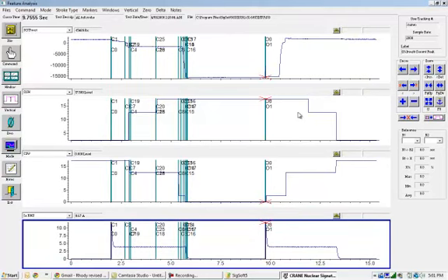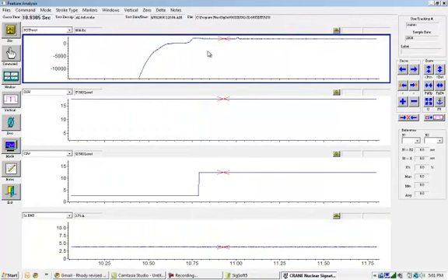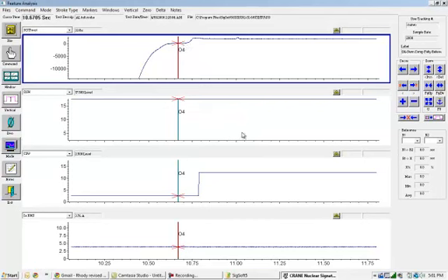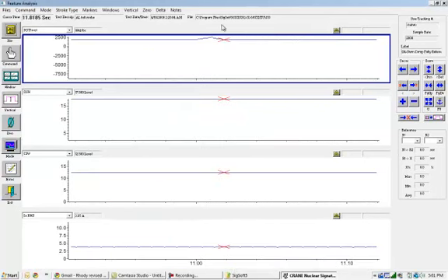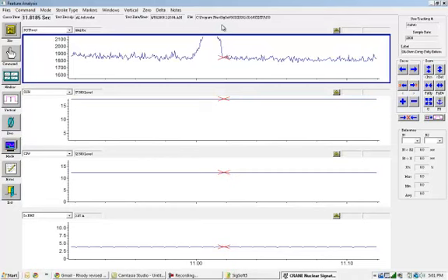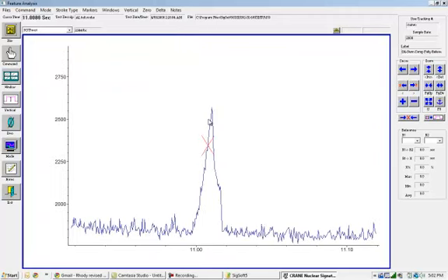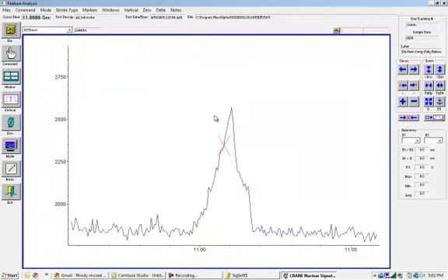All right. Since there's no unseating on this valve, we're just going to look at the ramps here. I'm going to mark this O4 just for now, and we'll look a little closer as we get more marks on there. We do have a bit of, I wouldn't call it an unwedging event. I'm going to turn this into one window just so I can see better. We do have some sort of unseating load. It might just be a starting friction.